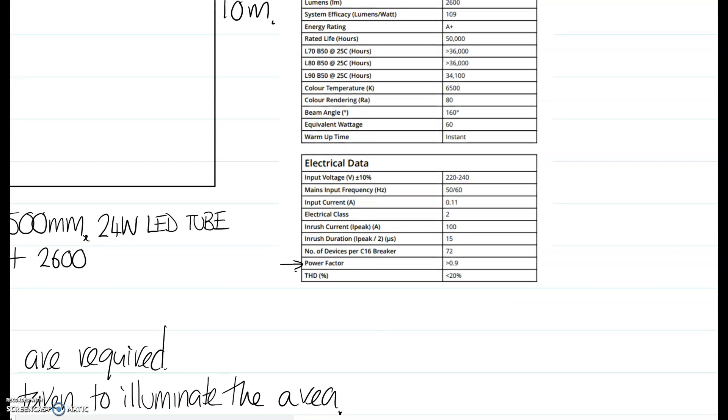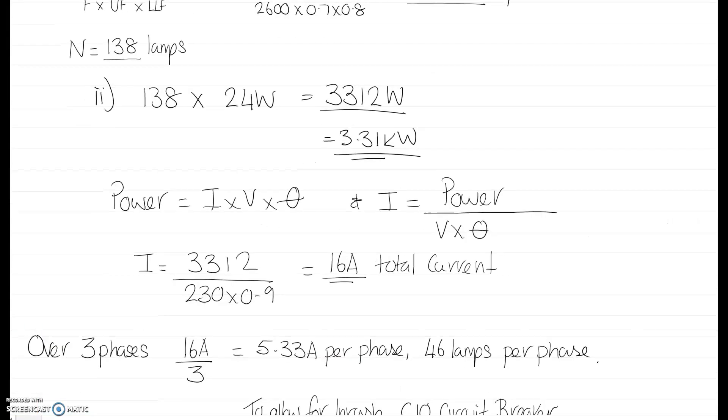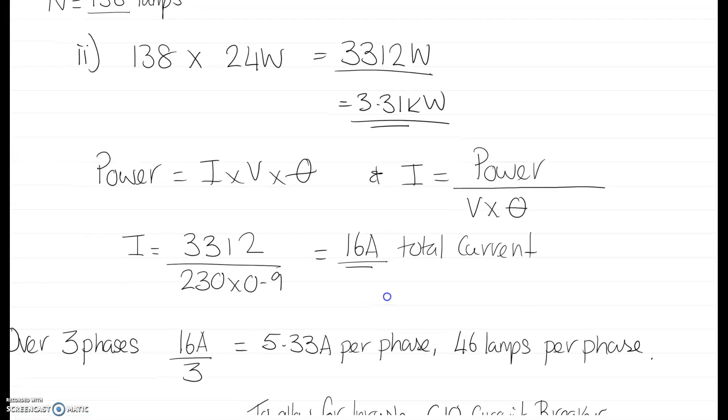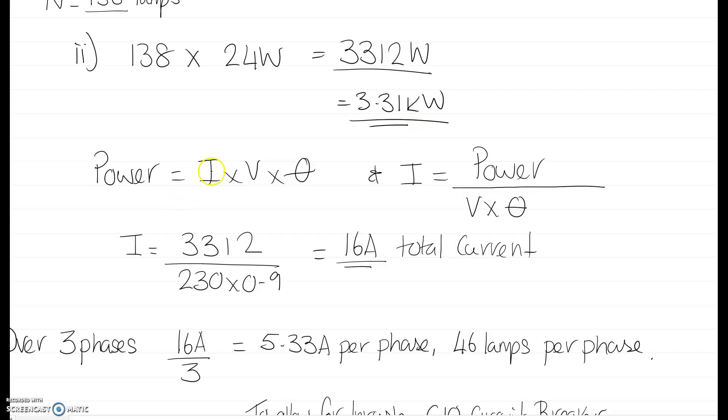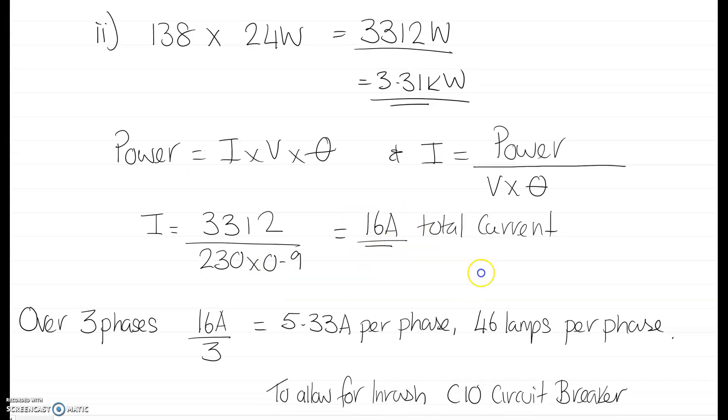Let's have a look and see how we can work out the current on this now. We know we've got 3.3 kilowatts total power. Power equals I times V times power factor. We're going to set the power factor at 0.9. We rearrange the formula for I. Power is divided by volts times power factor, so there's 0.9 worst case scenario, and we get a total current of 16 amps.